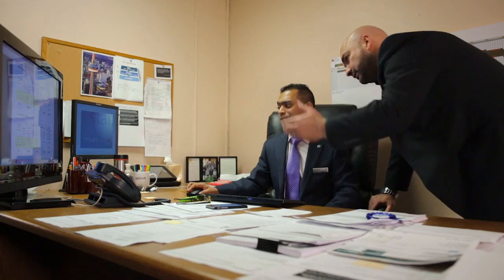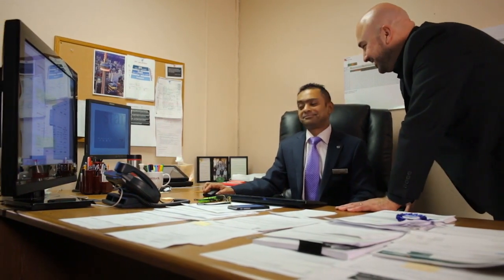As the Grundfos team, when we go out and inspect any site, we look for two main things. We look for pump efficiencies, the energy savings, and we also look for pump performance. In terms of the energy savings, we do calculations in two steps. The first step is we go in and collect the data from the pump. We do some calculations based on our experience, based on similar studies that we've done before, and provide our customer with an initial report called the Booster Check Report or Energy Check Report. That report will tell the customer the potential savings we have in their equipment, and it's fairly accurate.